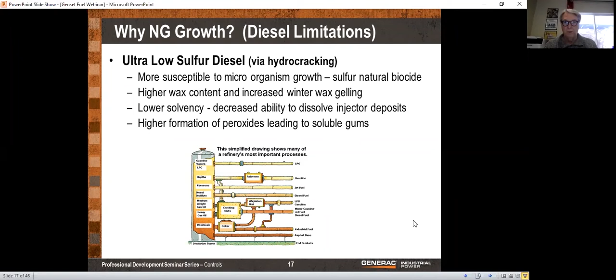We also get higher wax content, and it's easier for the fuel to gel. You can read the rest of those. We wish we had the high sulfur diesel back, but that's never going to happen. One thing we need to also recommend is that you do not use biodiesel. Biodiesel has a very short shelf life, so if you're an over-the-road trucker or something, yeah, use it, it's great. But if you put biodiesel in your generator and it sits there for months, that biodiesel is very unstable and will break down and likely lead to clogging of the fuel filters in a generator that simply isn't going to start.